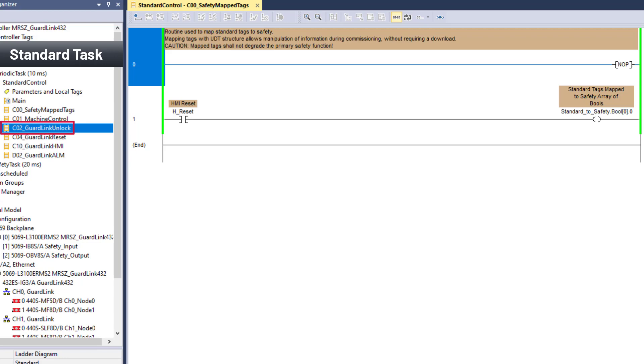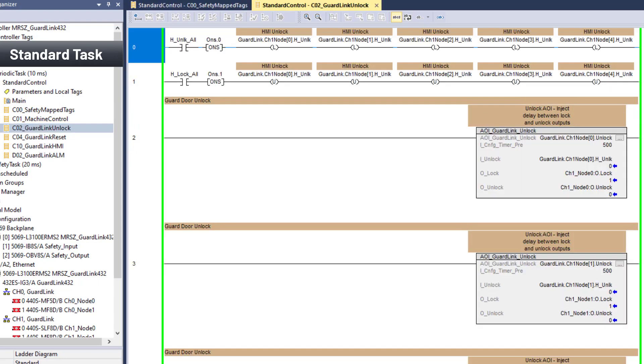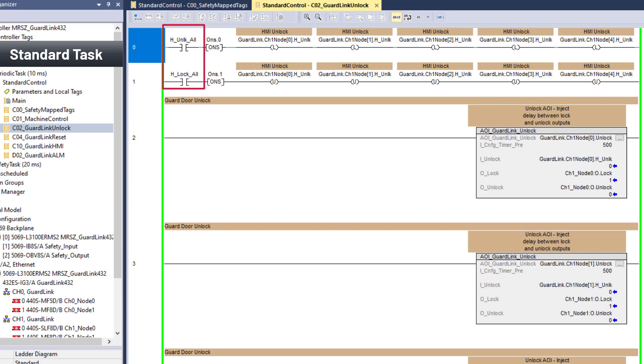Double-clicking on the C02 GuardLink unlock routine, the locking guard doors can be unlocked individually using the channel node unlock bits. Rungs 0 and 1 provide the capability to unlock and lock all locking guard doors. Rungs 2 through 6: the standard output for GuardLink has both a lock and an unlock signal. Typical programming would drive the lock and the unlock as inverted signals.